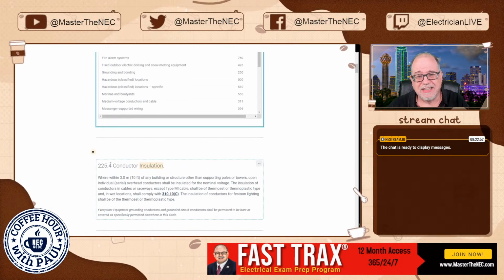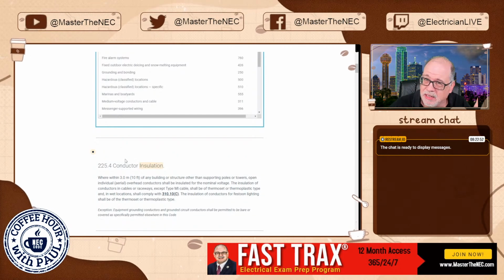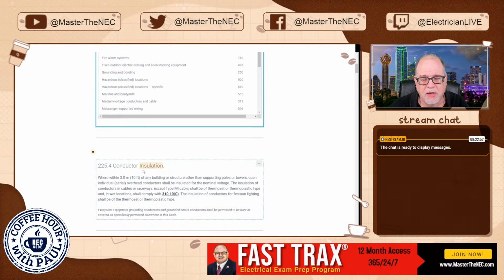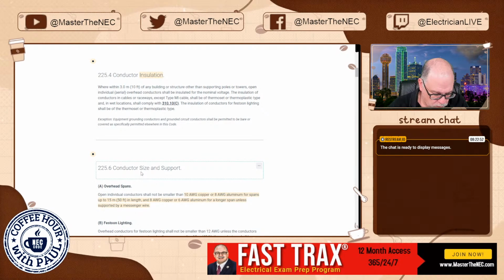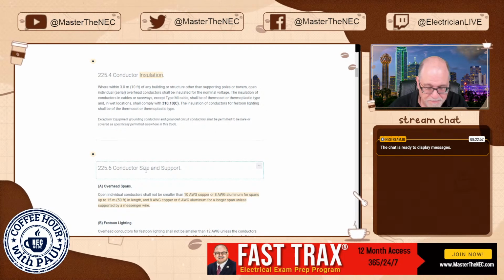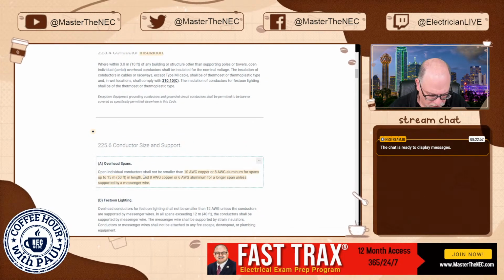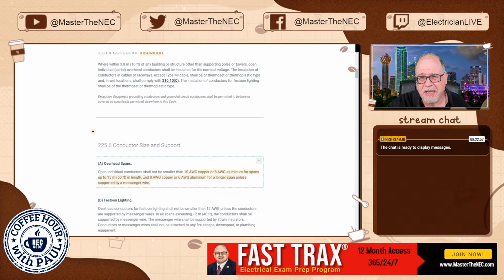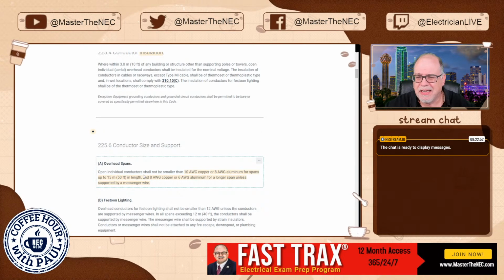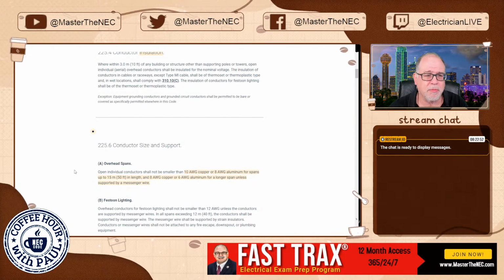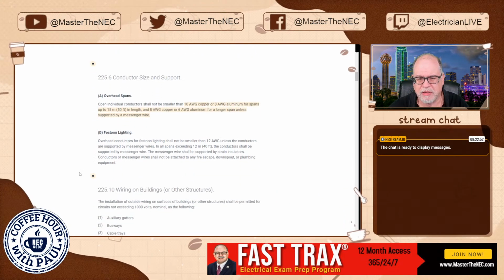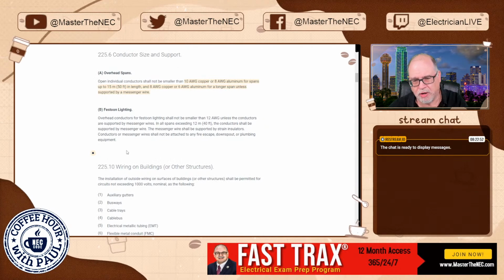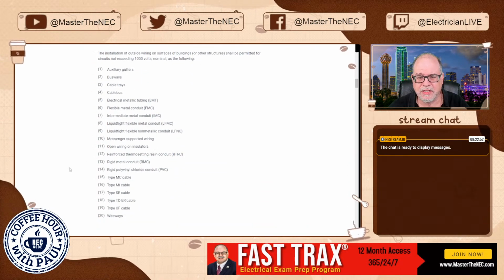Now, I will note that 225.5 was deleted because that was also dealing with over 1,000 volts, and now that's going to be covered in 235. But also, we removed 225.7 because it was redundant. It's already covered within 210 and all of this. So it really wasn't necessary. So that was removed from the 2023 edition of the National Electrical Code. So if you wonder why they're gone, that's why. They were redundant and unnecessary.